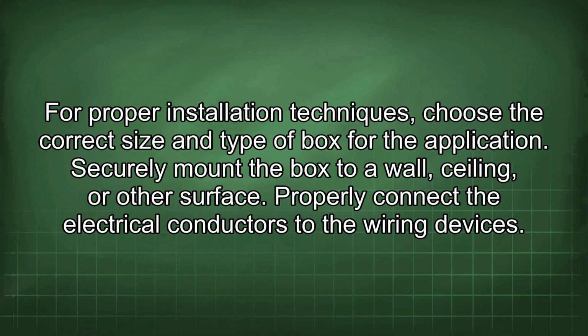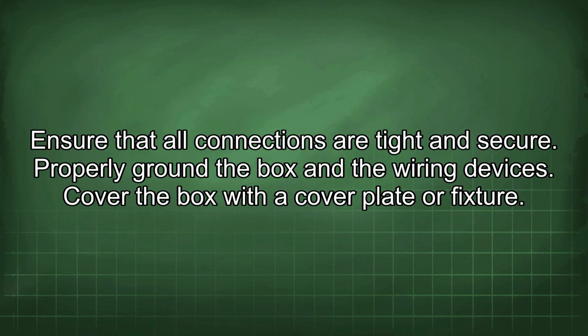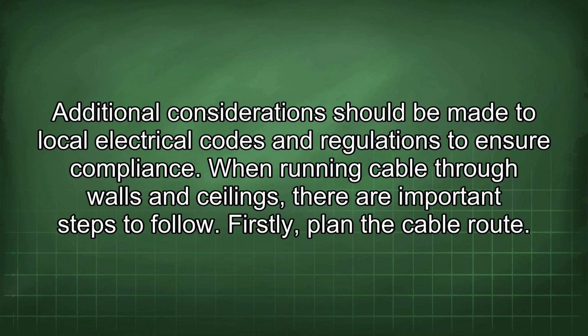For proper installation techniques, choose the correct size and type of box for the application. Securely mount the box to a wall, ceiling, or other surface. Properly connect the electrical conductors to the wiring devices. Ensure that all connections are tight and secure. Properly ground the box and the wiring devices. Cover the box with a cover plate or fixture. Additional consideration should be made to local electrical codes and regulations to ensure compliance.